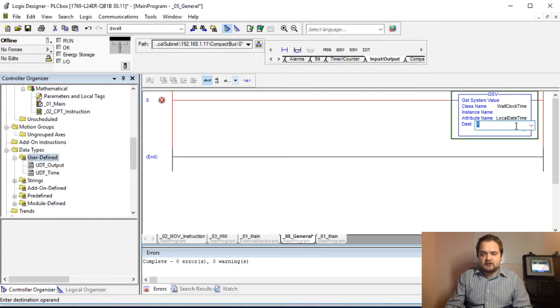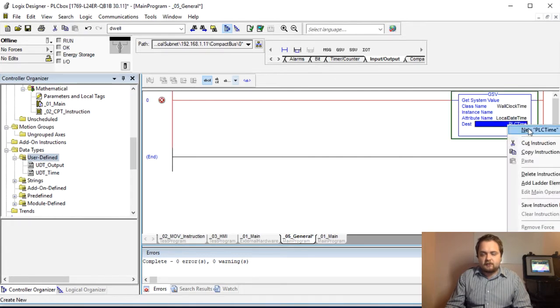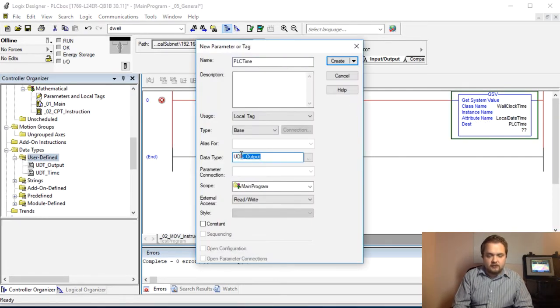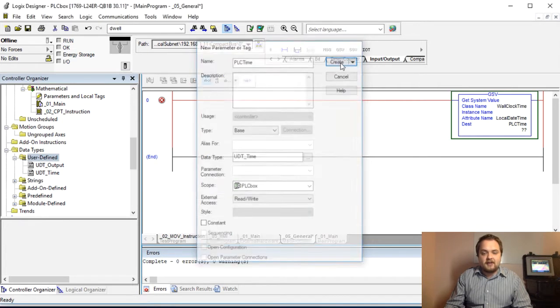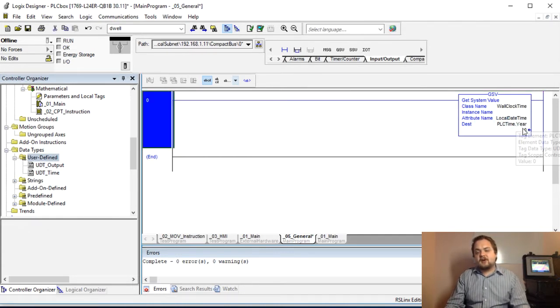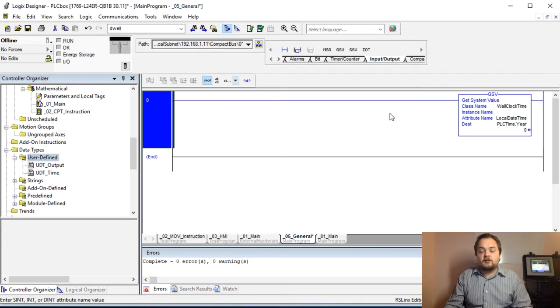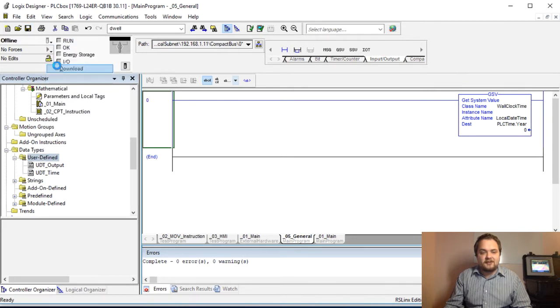We set the source attribute to Local Date Time and the destination is going to be our new tag. We need to create an instance called PLC_Time, of type UDT_Time, and make it global on the main PLC-scoped tag. The destination needs to begin with dot year — it will automatically populate all the other registers defined in the UDT, so don't worry that it's only showing dot year. Let's save this program and go online, then download to the PLC.